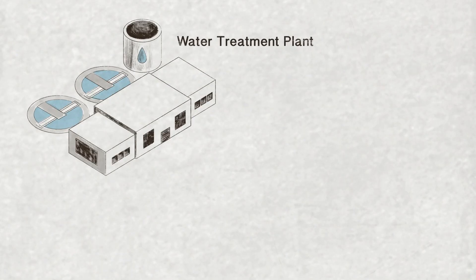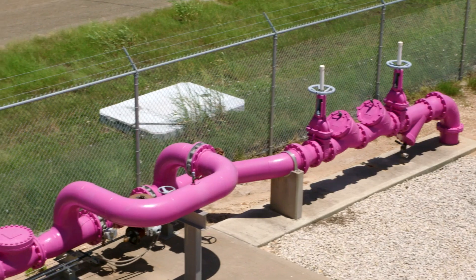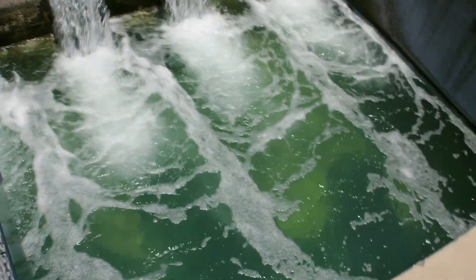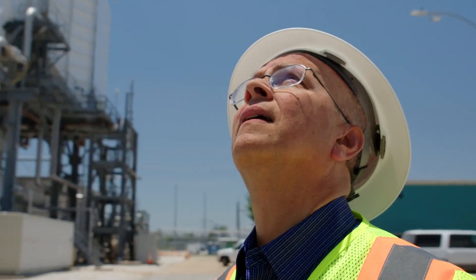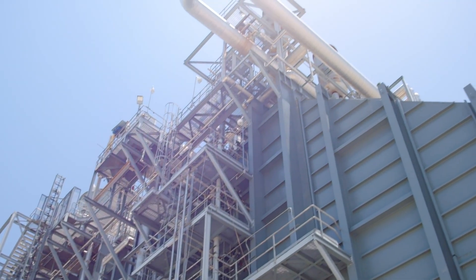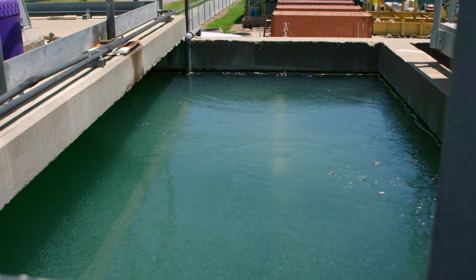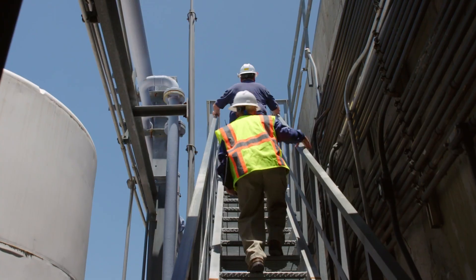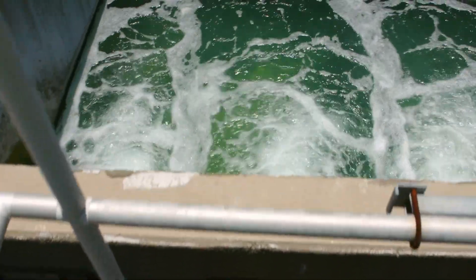We are doing our part here by supplying our highly treated wastewater — what we call reclaimed water. This particular plant uses about 50 million gallons of reclaimed water per month. By switching to reclaimed water, we save the drinking water for drinking purposes and use the reclaimed water for cooling. The flow right now is about 2,200 gallons a minute because of the summer demand — it is very hot, over 100 degrees.